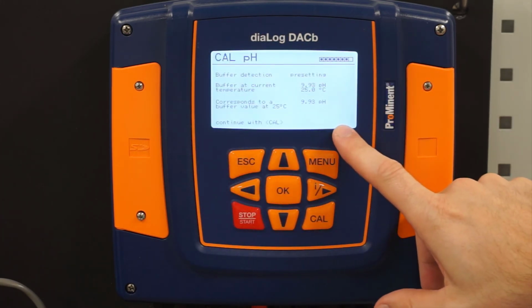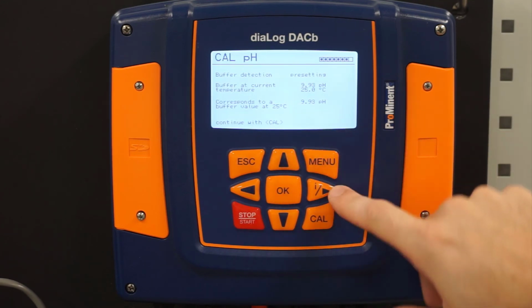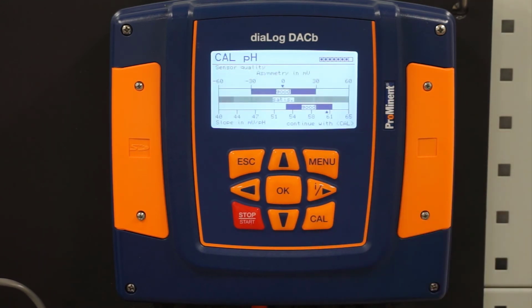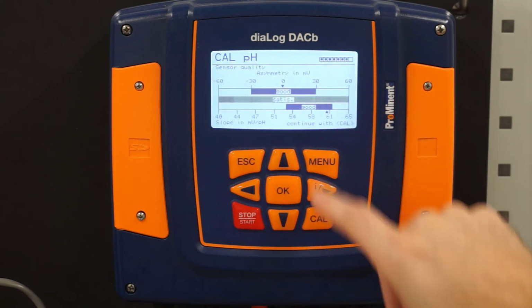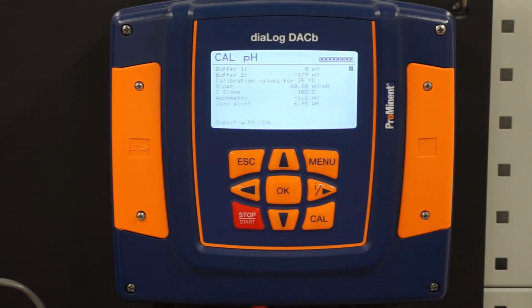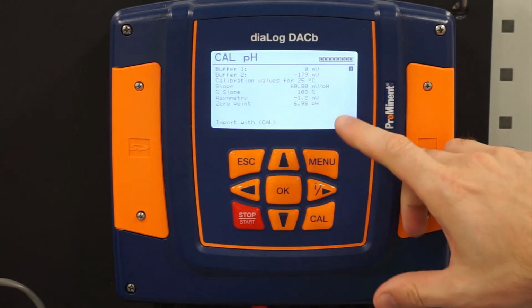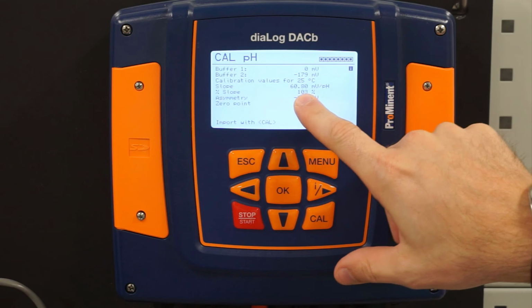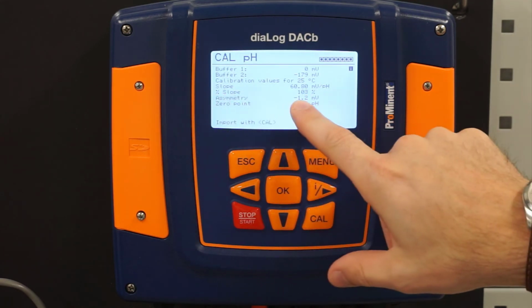Okay, this gives us just the data on that buffer 10. It actually is seeing 9.93 pH. We'll continue with calibration. This will tell us what our sensor quality looks like. This screen is a very important one. The one thing we want to look at is this right here, our slope percentage.